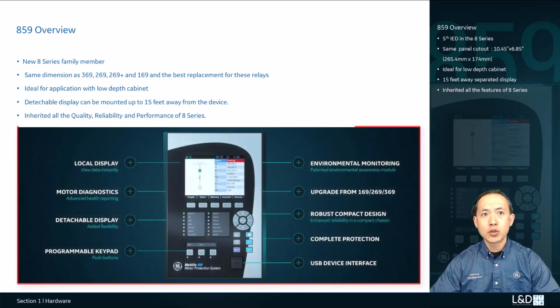It inherited all the quality and reliability features of the 8 Series, such as the IPC 610 Class 3 manufacturing, 100% board-level ESS testing, environmental stress screening, and standard harsh environmental coating, etc. For the other performance features, please refer to the 8 Series 100 overview video. 859 also inherited the advanced motor monitoring features from the 869 relay, such as ESA, electrical signature analysis, broken rotor bar, and stator interturn, etc.